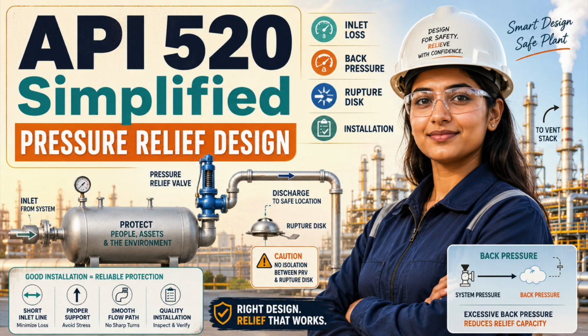You also need to distinguish between pop action and modulating pilot operation. A pop action pilot drives the main valve rapidly toward full opening. A modulating pilot opens only as much as needed to satisfy the required flow. Neither is universally better. The correct choice depends on process dynamics, relieving demand, inlet pressure loss, valve stability, and interaction with the downstream header. Remote sensing also needs to be understood honestly.